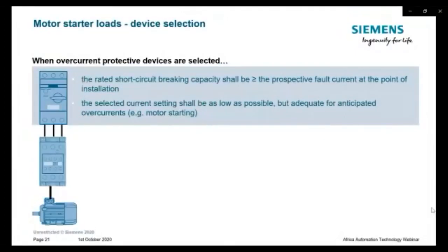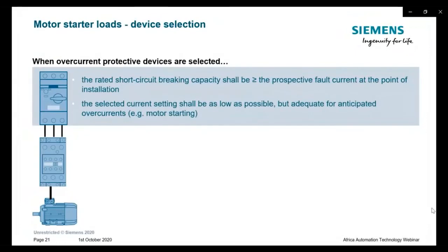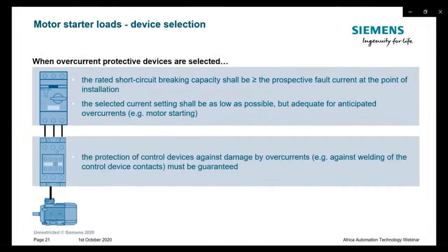Let's have a look now into the motor starter loads, specifically into the device selection. When overcurrent protective devices are selected, the rated short circuit breaking capacity shall be more or equal to the prospective fault current at the point of the installation. The selected current setting shall be as low as possible, but adequate for the anticipated overcurrents. So it's ensured that the motor starting goes smooth without any interruptions.